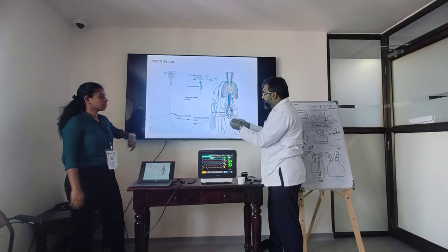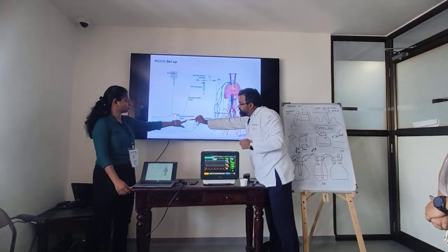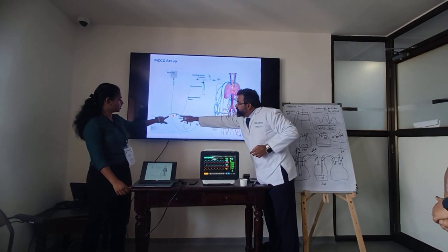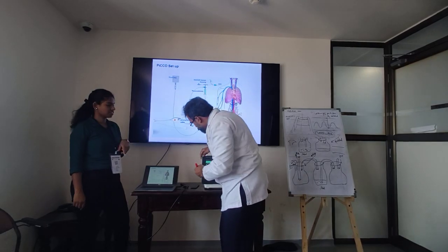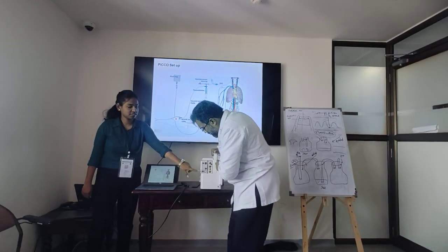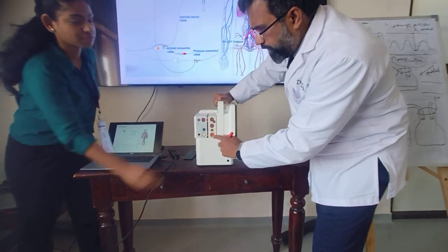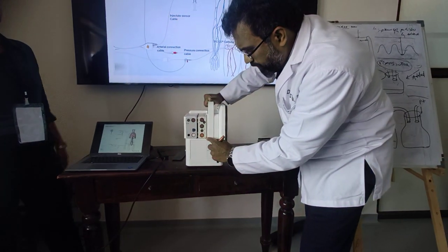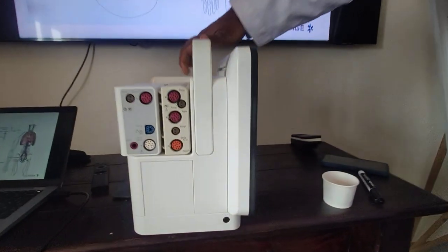There are 2 ports here, and this goes to this cable. This cable is what we require. Without this cable you can't use it, and without a monitor that actually says PiCCO. This orange one will not work. It needs to have PiCCO written on it. You can see it written PiCCO, so you cannot use just any module.